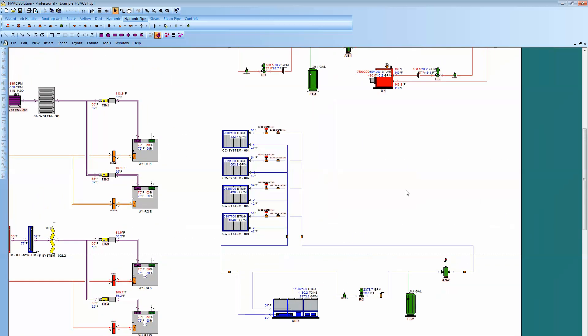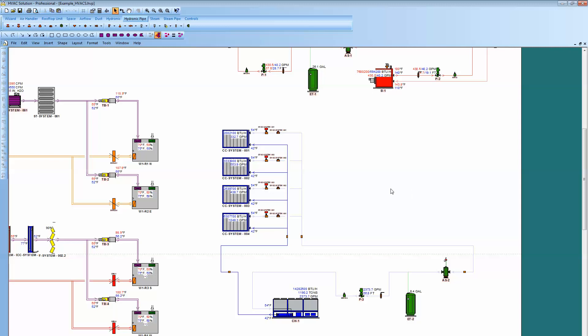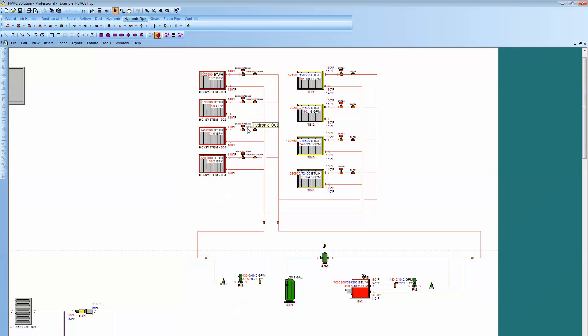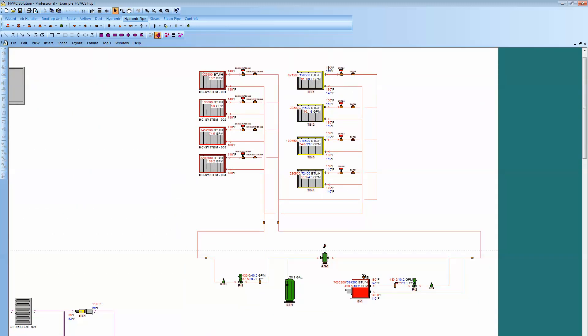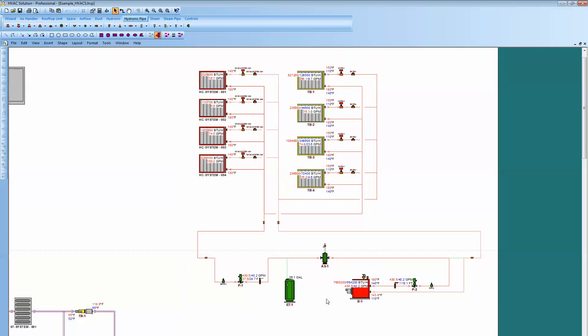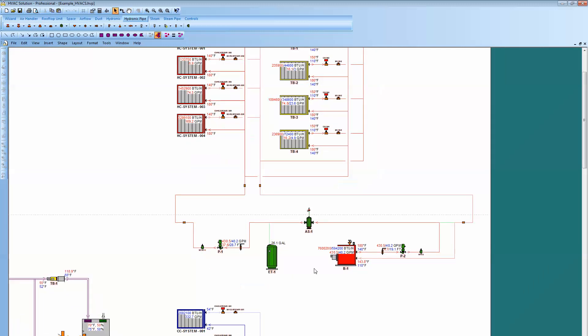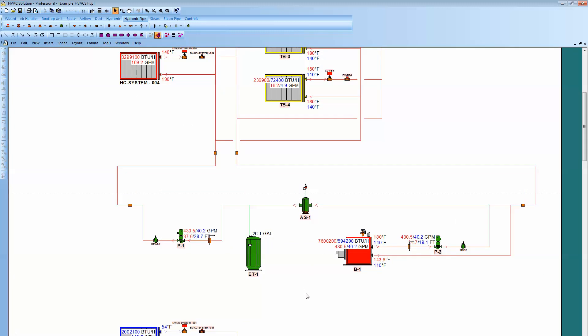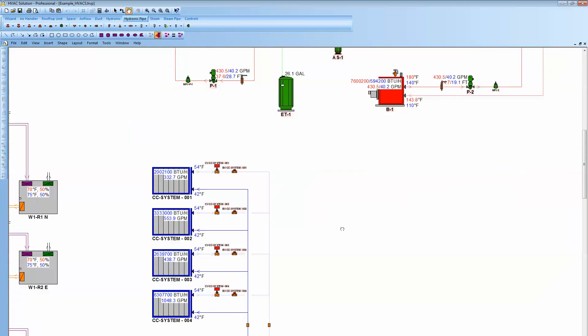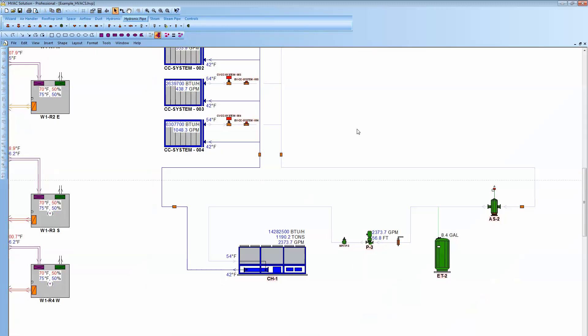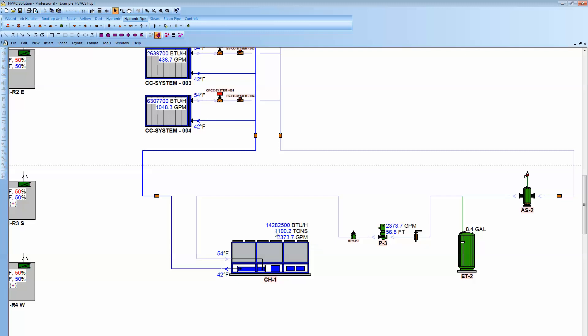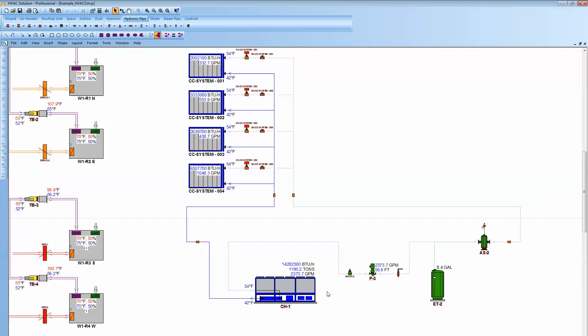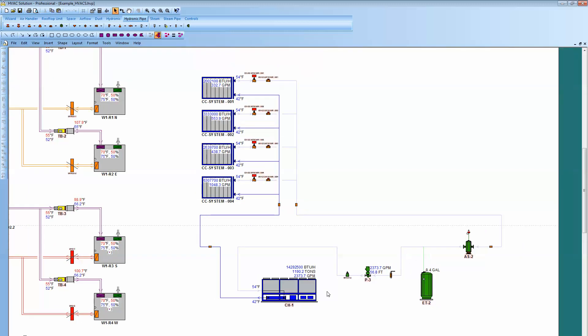And then over here to the right would be the hydronic cooling generation system and the heating. Now you can see these are the heating coils and here's the reheat coils. Now whatever the load program showed, as far as heat loss, how much we needed, that's the number that better be here on my heating load. And then down here below on the cooling load, whatever the load said, it should have said close to 1190 tons for my loads program. That's how I can check to see if in fact all the data is correct here.